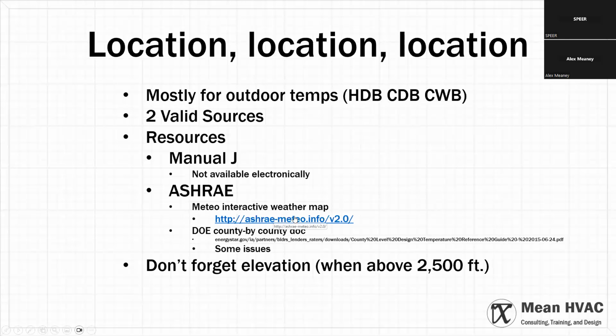But this page here, this tool here that gives you access to the raw ASHRAE data, they have what are called peak dehumidification conditions, which are like peak cooling conditions, but they are for the most humid day and not the hottest day. If you're sizing the dehu, not the air conditioner, the dehu, you can use those conditions in a load calculation to determine what the need is.